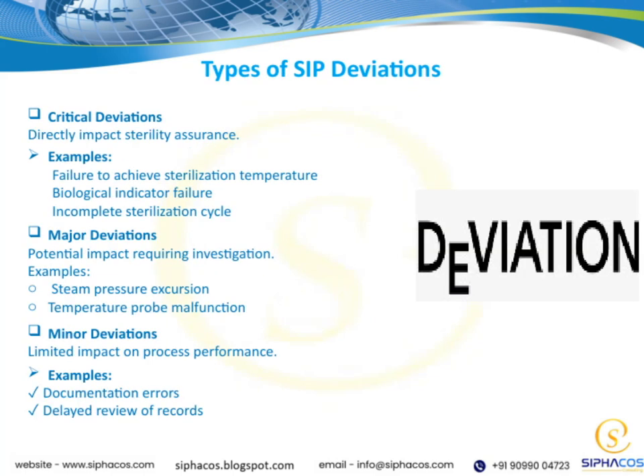When we talk about SIP deviations, we're looking at three main types: critical, major, and minor. Critical deviations hit sterility assurance directly. Think of things like failing to reach the right sterilization temperature or a biological indicator not passing. Major deviations might not cause immediate harm but still need investigation, like a steam pressure spike or a faulty temperature probe. Minor deviations have limited impact, often involving paperwork issues or delays in reviewing records. Each type matters, but they carry different levels of urgency.